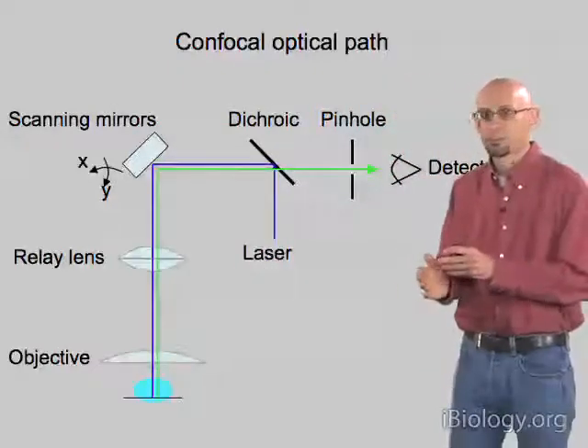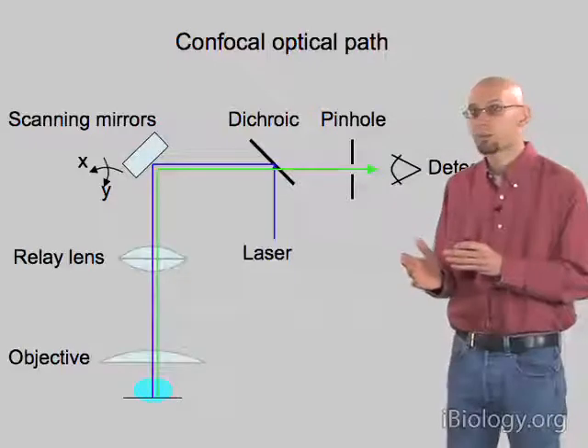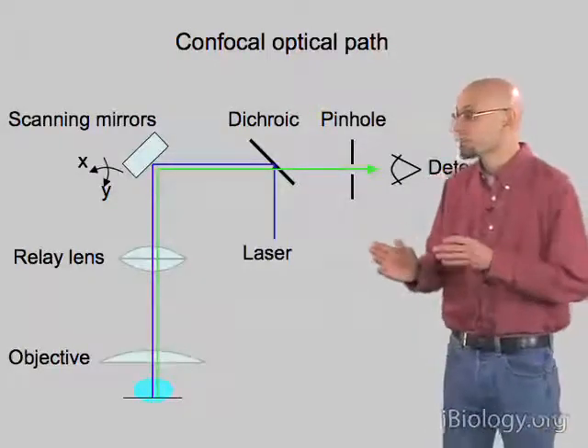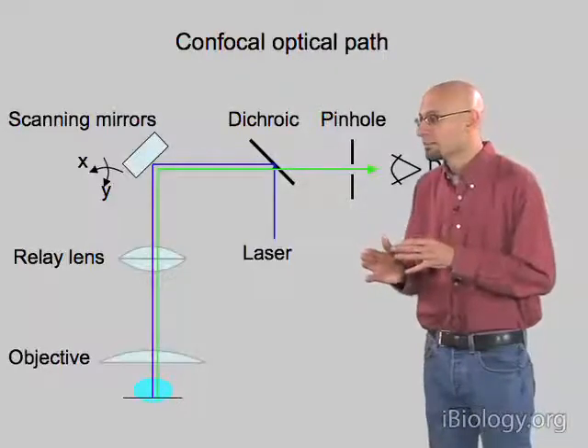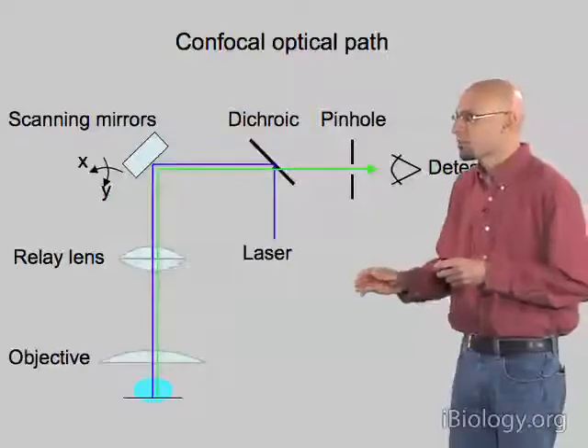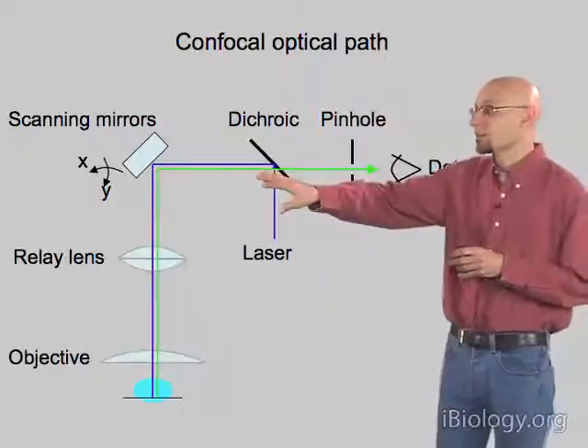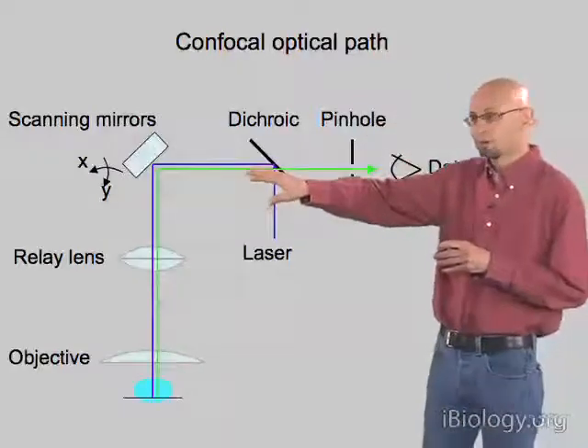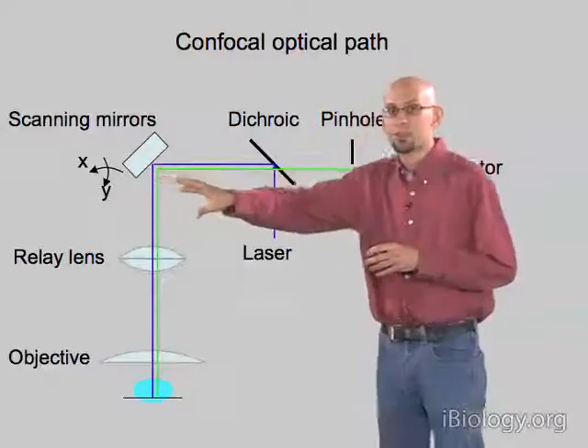If you imagine what's going on with the light emitted by that spot — it's going to come out, be collected by the objective, and come out at the same angle it entered, because the objective maps angles into position. So the light that comes from that excited spot is coming out at the same angle that the laser beam entered. If we don't move these mirrors, that emitted light will be reflected by these mirrors along exactly the same path that the laser came in along. The light is always coming in the same direction regardless of what spot it came from, because the scanning mirrors exactly undo the angle change applied to the illumination light.